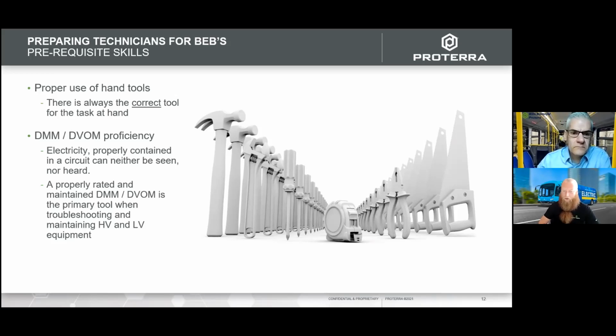Also, knowing that you have the properly rated digital multimeter is another important factor. Technicians may have a digital multimeter on hand—typically stateside we call it Harbor Freight—but it may be rated incorrectly for the task at hand. Some of those are 400 volt ratings, maybe 600 volt, but typically on Proterra buses we need 800 volt or more. On top of that, your leads are another important aspect of this.